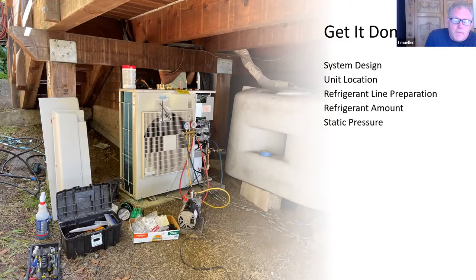This is another one where we've probably all had HVAC subcontractors show up to replace a heating system. They look at the existing heating system and say, okay, that's 60,000 BTUs per hour, so we'll put in a 60,000 BTUs per hour system. Well, if you're going from a gas furnace to an electric heat pump and you just swap it out size for size, you're going to do the client a huge disservice by giving them an oversized system that's not going to be efficient at all.